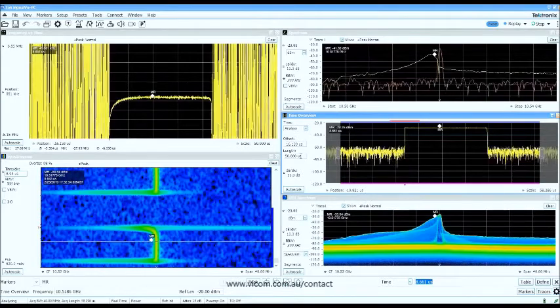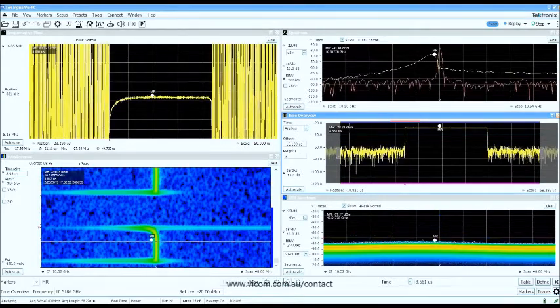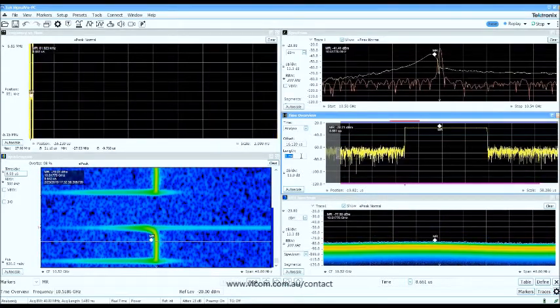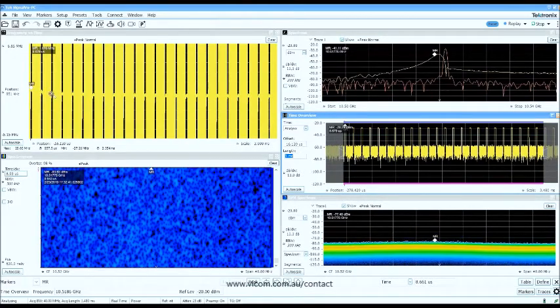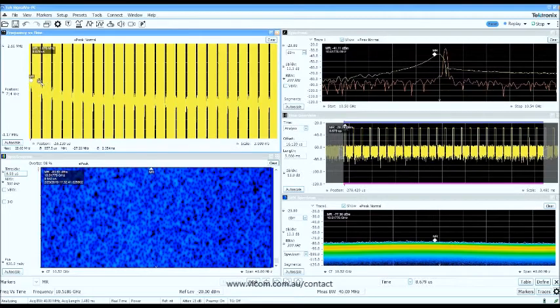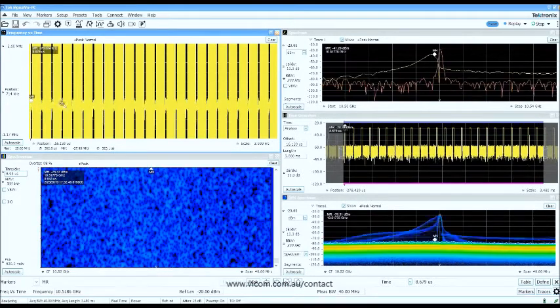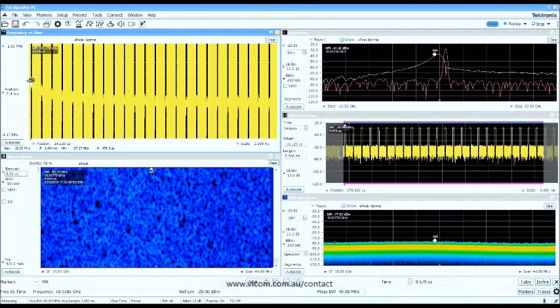But if we capture some more pulses over time, let's grab, say, 3 milliseconds worth of data. If I first pull the trigger, and again zoom in a little bit vertically here, you can see that characteristic in the frequency deviation versus time, where those first pulses are slightly higher in frequency, and then it works its way down again.